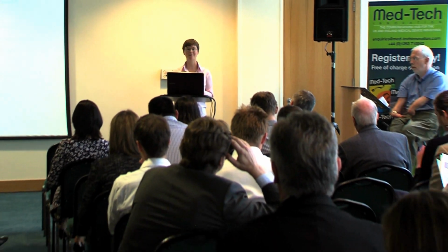But I think in about 3 or 4 years' time there will be a new 62366, which will be in 2 parts. The first part will be 62366 as it is at the moment, just the statements of what you will do, and there'll be a second part which will be a rejigging of TIR 75 and this is how you should do it. And then I think it will be more streamlined. That's my view about where it's going in the future.